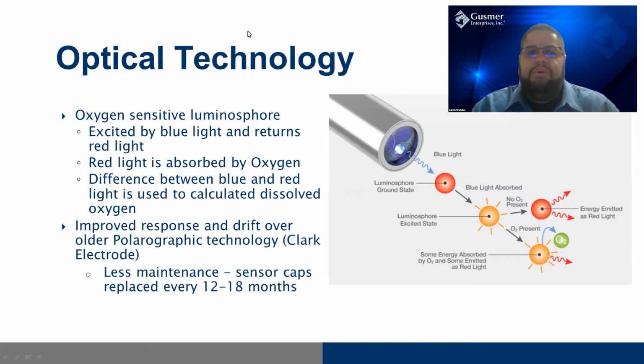It's an oxygen sensitive chemical, and there's a blue LED inside the sensor. That LED will shine on the luminophore. The chemical will go into an active state, and then it will release red light as it comes back down to the ground state. That amount of red light is picked up by the sensor. In the presence of oxygen, when that red light is released, some of that energy will interact with oxygen. What that oxygen does is reduce the amount of red light emitted by the luminophore, and so the sensor can pick up that reduced amount of red light and determine how much oxygen is in the environment. That's how the optical technology works. Again, with the Visiferm MA and the Visitrace MA, you only have to replace the sensor cap every 12 to 18 months, and you would probably only have to calibrate these sensors every 3 or so months. So it's great technology.